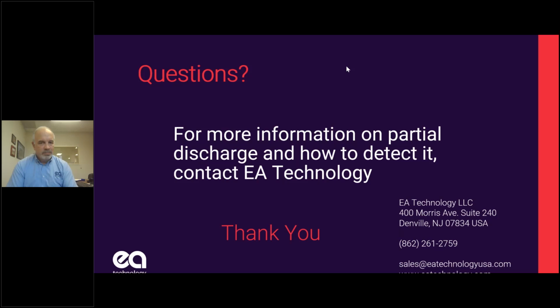Can multiple cables be tested at one time? Well, if you use full-time monitoring, you can hook up with our system, I'm going to say, 40 three-phase cables all at the same time, and test all of them. If you're using one of the handhelds, we either support 3 HFCTs, which allow you to do 3 phases at one time, or with the +2, you could do one at a time.